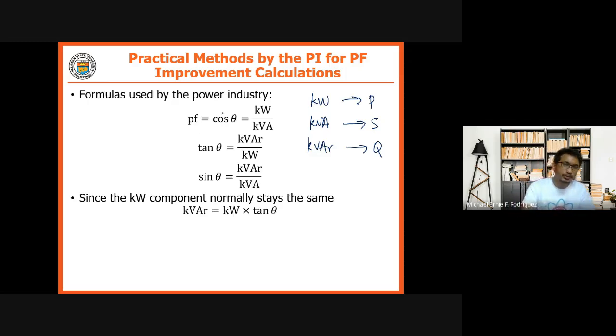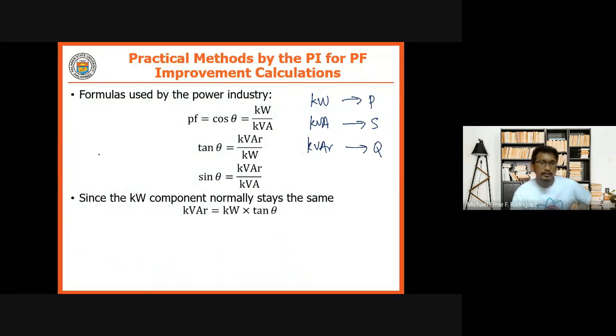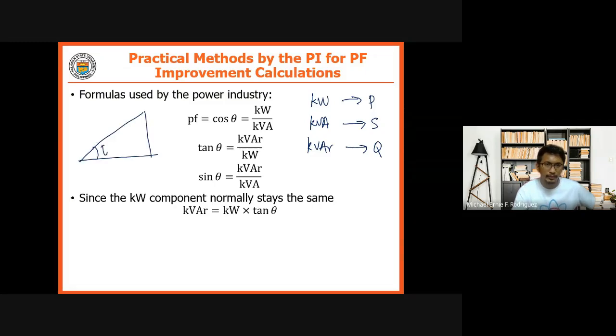So for the power industry, your PF is equal to kilowatts over kVA, basically P over S. Tangent theta, wala pa rin dito sa triangle, kaya i-triangle ulit natin: kilowatt, kVAR, and kVA. So cosine theta is kilowatt over kVA. Tangent theta is TOA, opposite over adjacent, so kVAR over kilowatts. And sine theta is kVAR over kVA, opposite over hypotenuse.